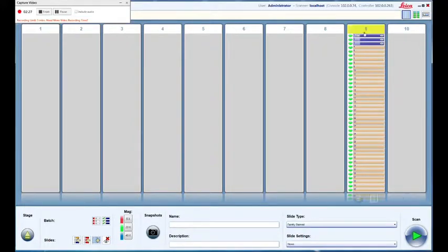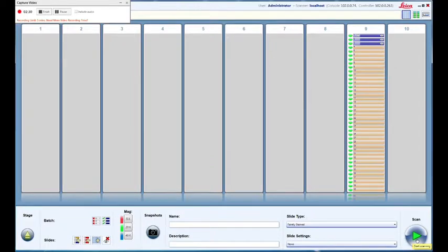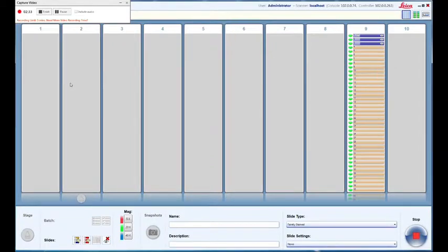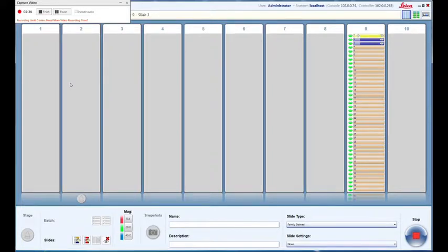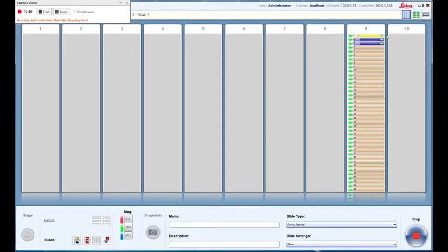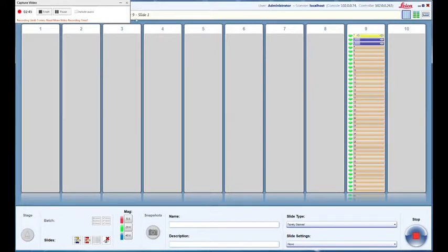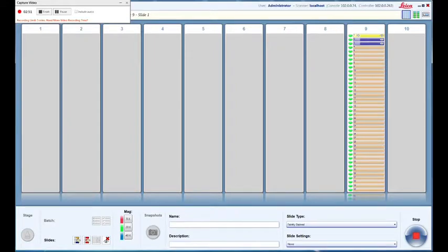Now everything's been viewed as dark blue and there's an eye icon there. Now we are able to scan. The scanning process takes a couple minutes depending on how big of an area of the slide was selected. Typically at this point, I will just walk away from the instrument for a few minutes and work on something else.